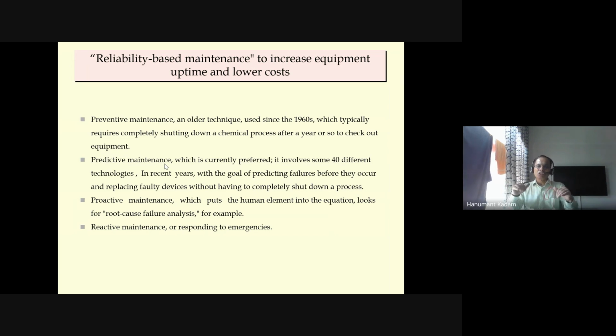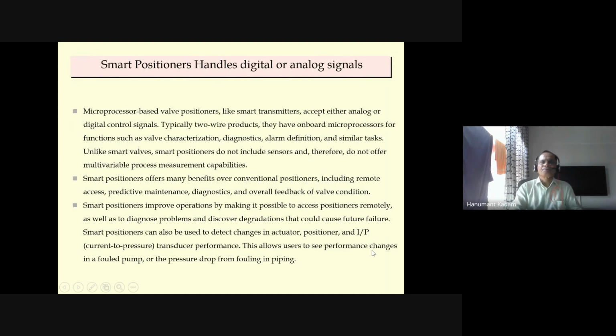So this is predictive maintenance, which is achieved through the smart valve positioners or intelligent valve positioners. Proactive maintenance means which puts the human element into the equation, looks for root cause failure analysis, for example. That is proactive. Then reactive maintenance, or responding to an emergency, means when the valve has stopped, remove it, and that is reactive maintenance. Why I have explained this is because in the control valve, a lot of maintenance was happening, and now we are getting relief through this technology, and the terminology used is predictive.